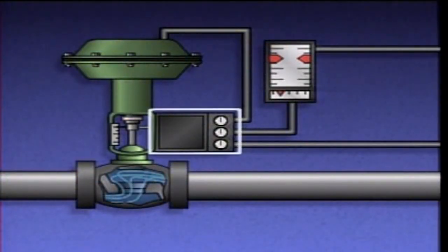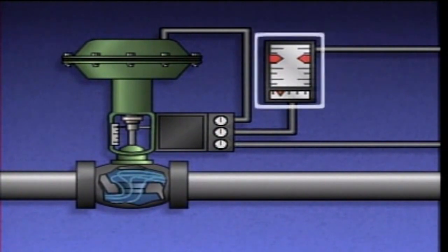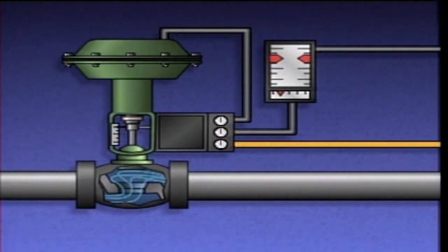When a positioner is used with an actuator, the signal from the controller goes to the positioner instead of directly to the actuator. The positioner controls a source of air that enters here and is sent to the actuator through this line.